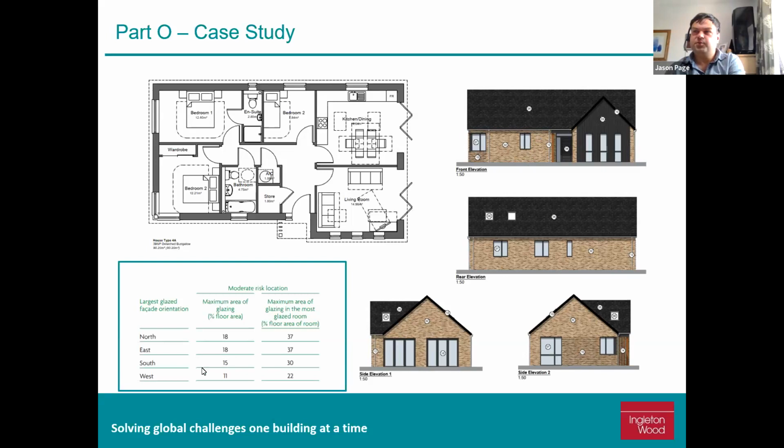it's the biggest facade for windows, and the west criteria is you need to be below 11%. So we still fail Part O. So we needed to balance removing windows with maintaining the amount of glazing on appropriate facade to mean our target was high enough to pass.